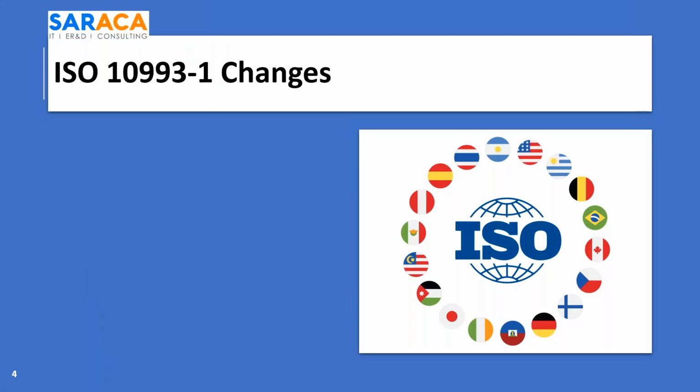Okay, some of the specific changes in 10993-1. It was actually released by ISO in 2018. It was approved here by AAMI on April 24th, 2020. It was approved by ANSI on April 27th, 2020.